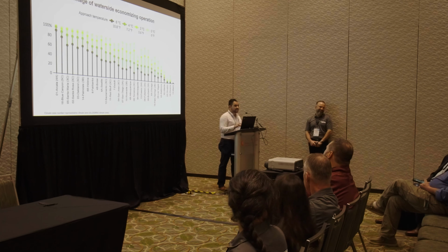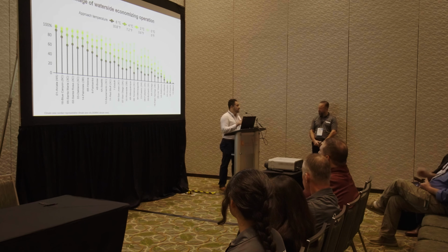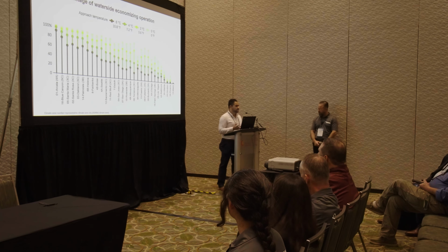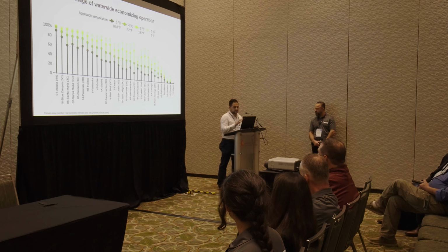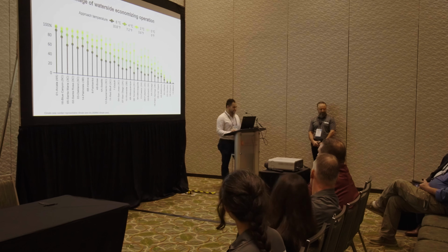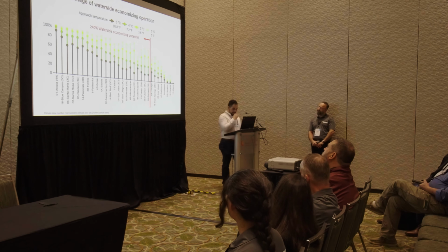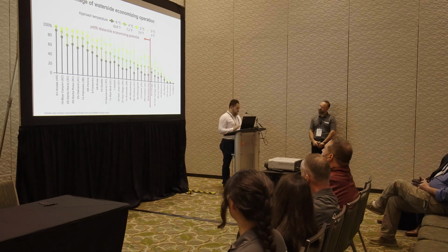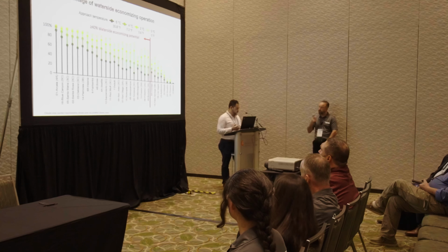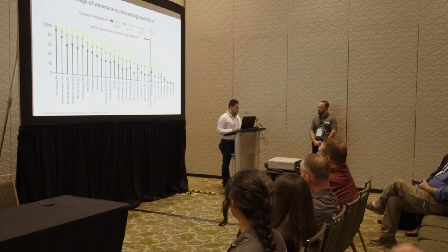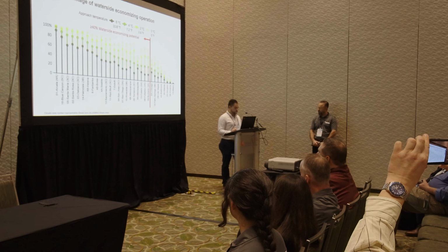But this is not to say that radiant systems are not high performing in Miami. There's still opportunity for cooling load savings, but it can't do waterside economizing. Can't use the cooling tower. Yeah, exactly. But in summary, 22 climate zones allow 40% or greater waterside economizing operation with a typical 7 degrees approach temperature.